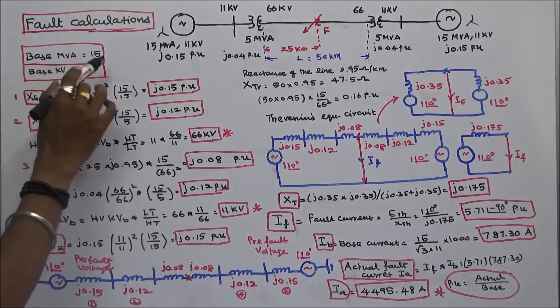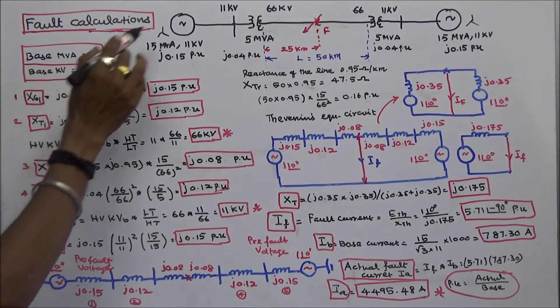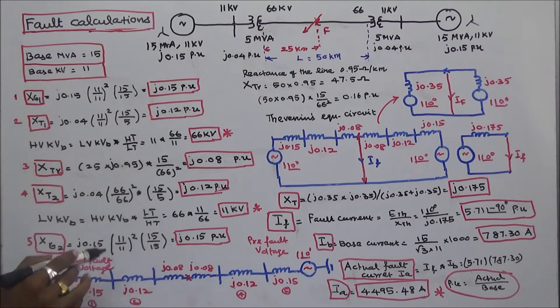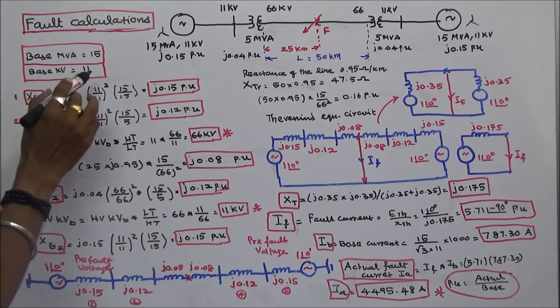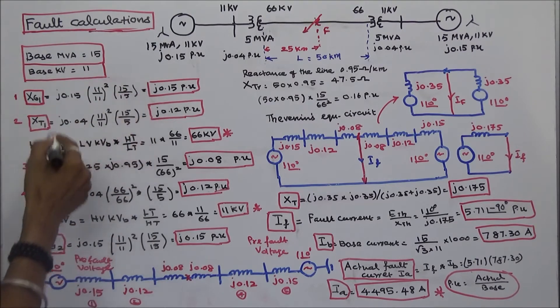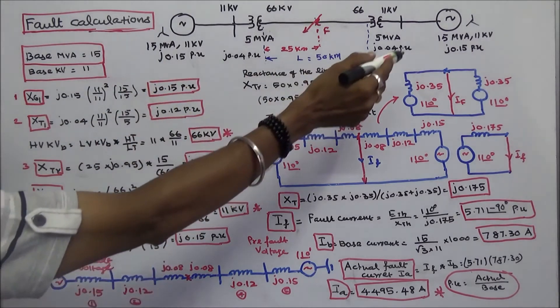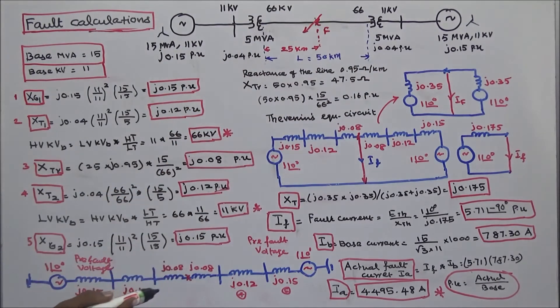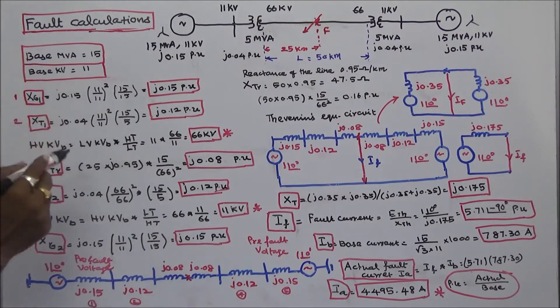The first step is to choose the base MVA and base KV. Base MVA is equal to 15. Base KV is equal to 11. Next, we calculate the per-unit reactance values of all components with respect to this base MVA and base KV.